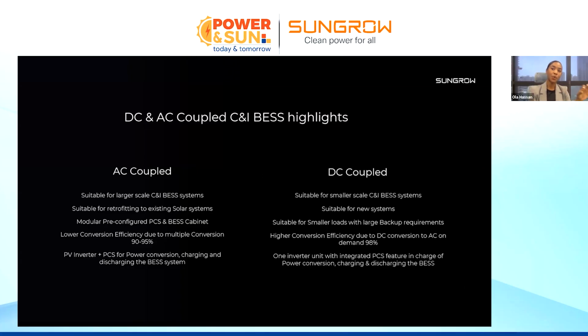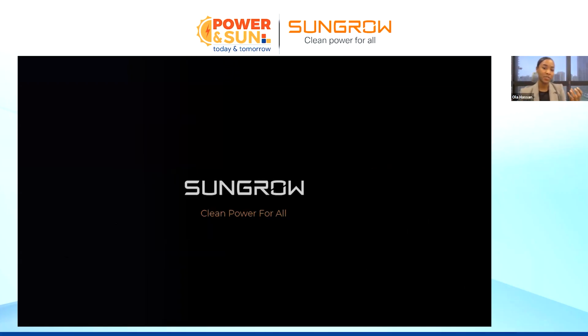So for the AC coupled, I want to highlight that with Sungrow, we can connect up to 20 units in parallel. So up to 20 units in parallel, if we are using the 255 or the 510, assuming we're using the 510, this is up to a 10 megawatt hour system. So this is suitable for bigger C&I system segments that are rated at 400 volts, while the DC coupled is suitable for the smaller segments. So by this, we have completed the introduction of both of the solutions.